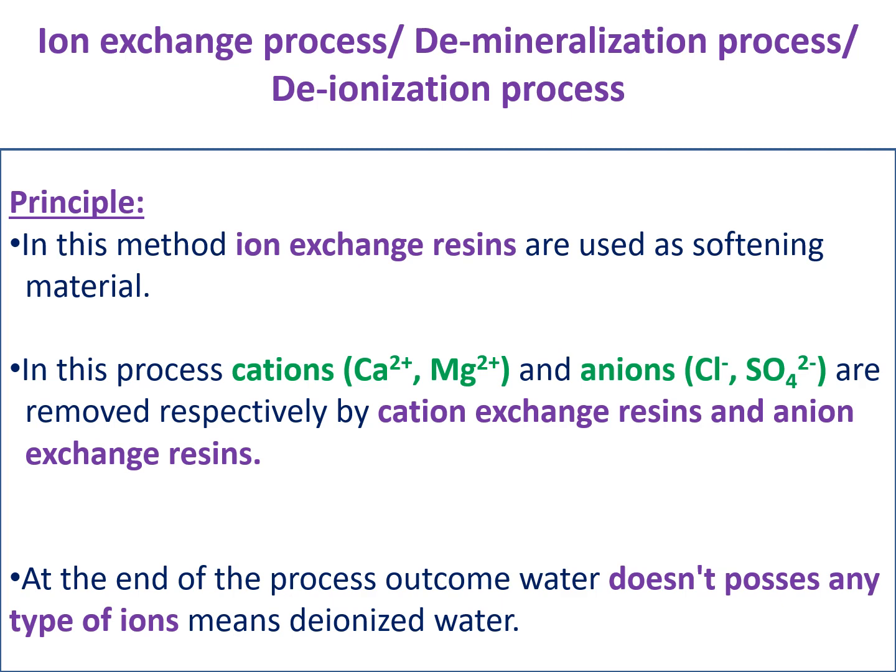The cation exchange resin exchanges all cations present in the hard water — Ca²⁺ and Mg²⁺ ions are exchanged by the cation exchange resin. All anions like Cl⁻, SO₄²⁻, and HCO₃⁻ are replaced by the anion exchange resin. Finally, the output water doesn't possess any type of ion — that is why this process is called the deionization or demineralization process.